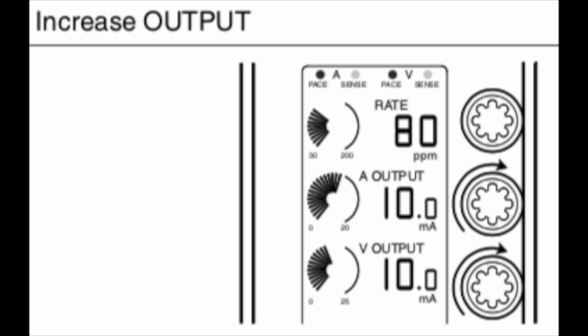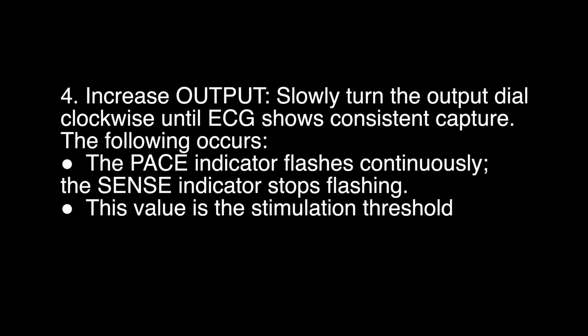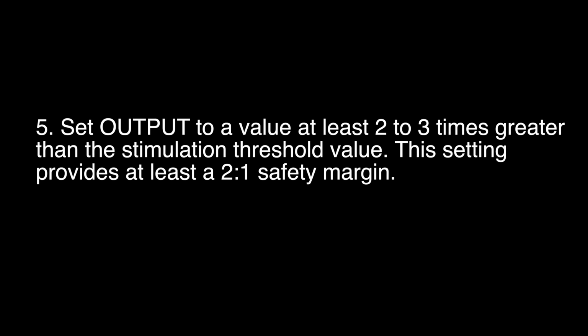4. Increase output. Slowly turn the output dial clockwise until ECG shows consistent capture. The following occurs. The pace indicator flashes continuously. The sense indicator stops flashing. This value is the stimulation threshold. 5. Set output to a value at least 2 to 3 times greater than the stimulation threshold value. This setting provides at least a 2:1 safety margin. 6. Restore rate to the previous value.